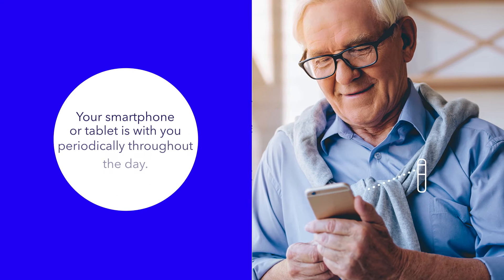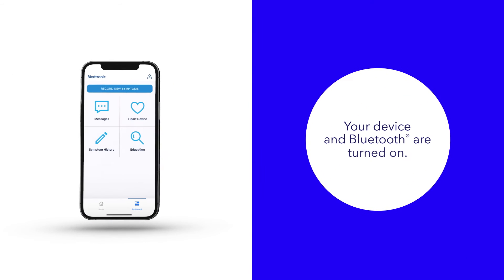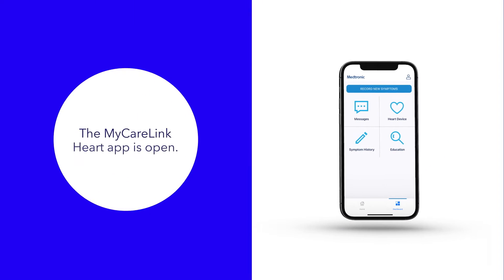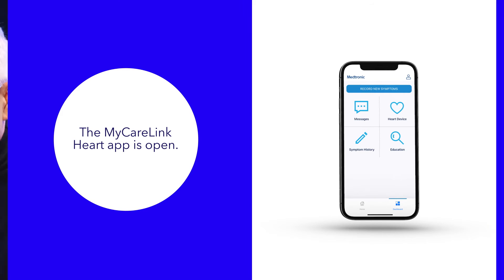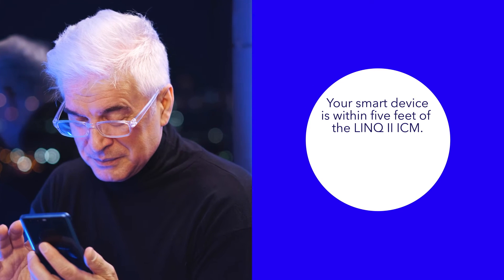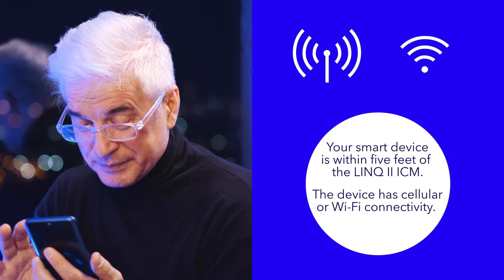First, your smartphone or tablet is with you periodically throughout the day. Second, both your device and Bluetooth are turned on. Third, the MyCareLink Heart app is open, either in the background or foreground. Finally, your smart device is within 5 feet of the LINQ II ICM, and the device has cellular or Wi-Fi connectivity.